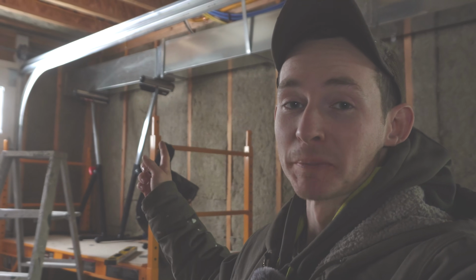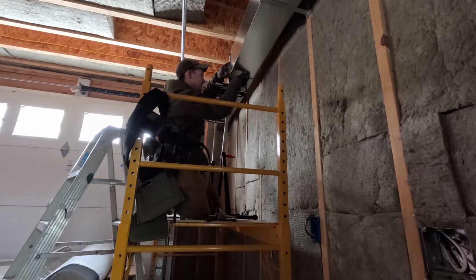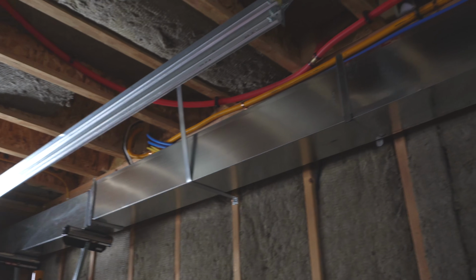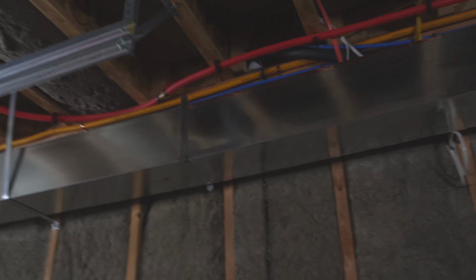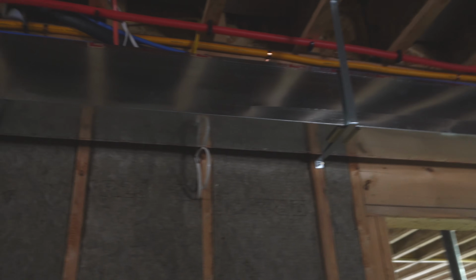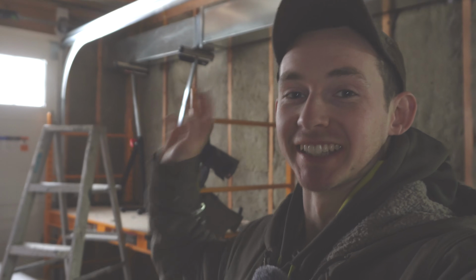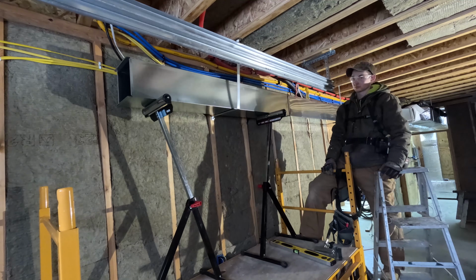With that last section mocked up, the whole supply trunk is finally temporarily fastened. I was able to mark where all the takeoff locations are going to go. Now we take it down, cut some holes in it, clean it, seal it, insulate it, put the takeoffs on, and put it all back up. Then finally the supply trunk will be up permanently and we can finish all our branches. I think this calls for a montage.